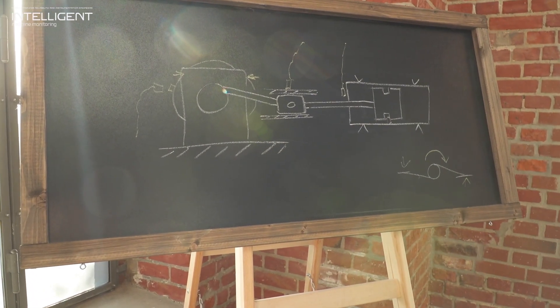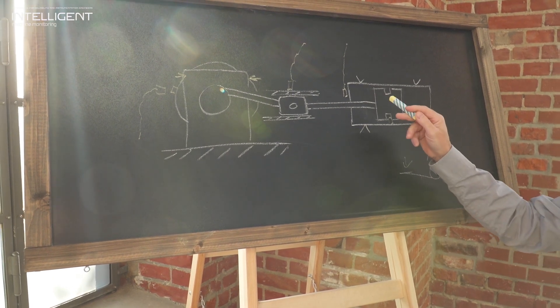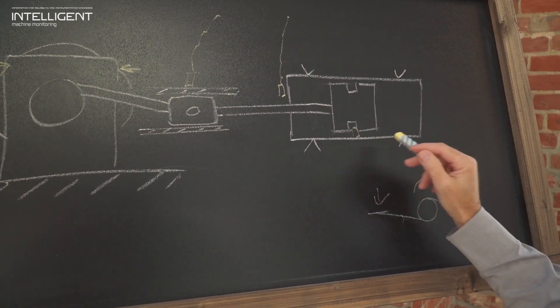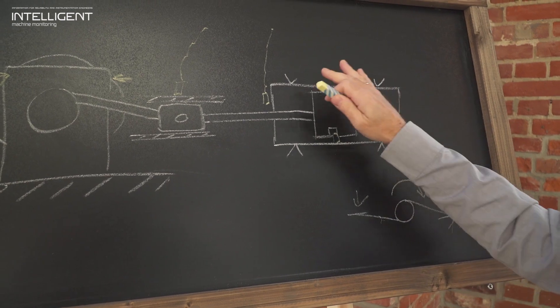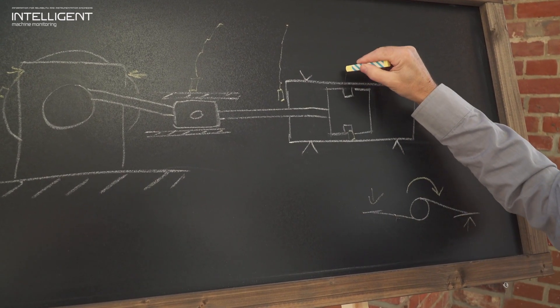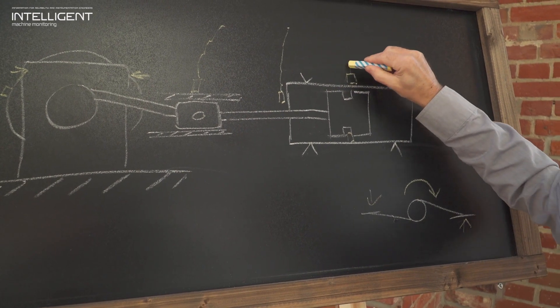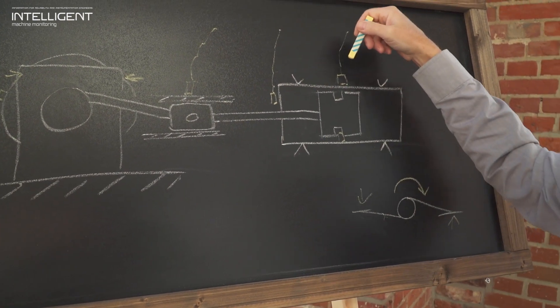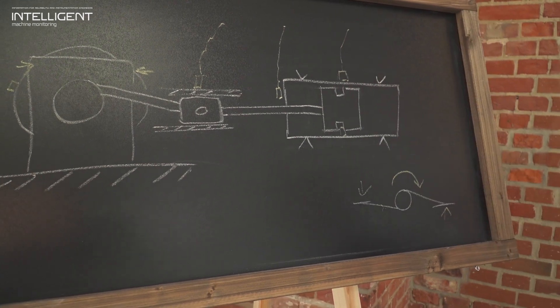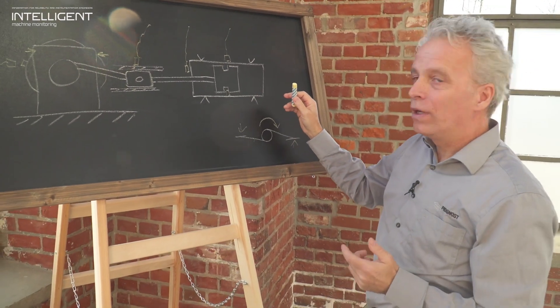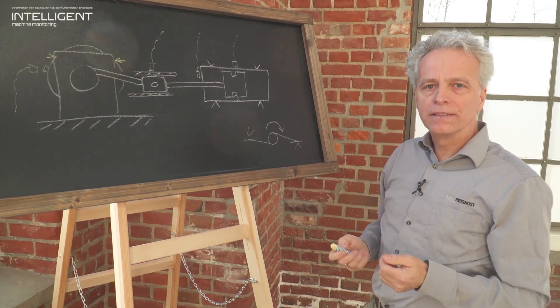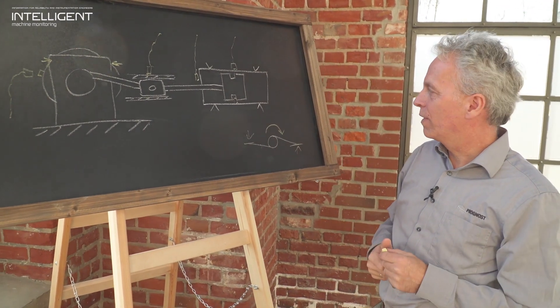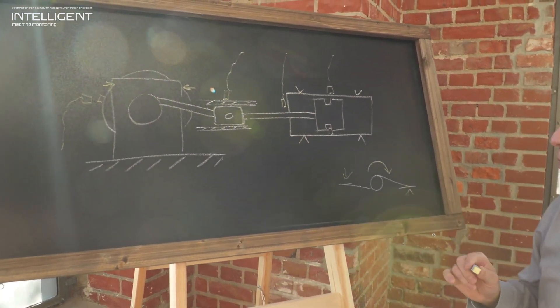Now we come to the components of the reciprocating compressors which statistically account for most of the problems, and that are the valves: suction valves and discharge valves. To monitor all the valves of one cylinder, we recommend to install one acceleration sensor in the middle between the valves at the head end and crank end, close to the suction nozzle. With this acceleration sensor we can pick up all impacts caused by the valves and also anomalies like for example clogged valves, sticking valves, meaning late closing valves, or broken valve plates.